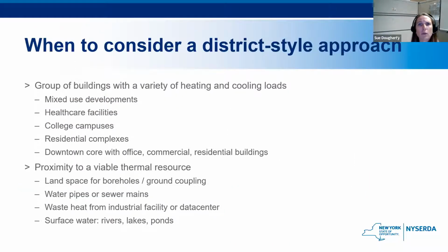So when should one consider a district-style heat pump approach? These are examples at the top of when you have a diverse set of heating and cooling loads—connecting those buildings together lets you share heating and cooling among them and bring down overall energy usage. Another consideration for a district-style heat pump system is proximity to a thermal resource, such as having open space in the right conditions to drill boreholes for geothermal. Another thermal resource that could be used is wastewater, or if you're close to a facility expelling waste heat, such as a data center or an ice rink, you can use that waste heat further down the line in another building that requires it. Surface water is also a great opportunistic thermal resource.